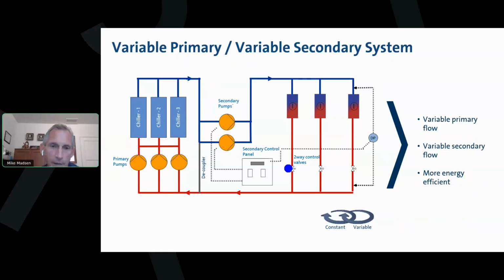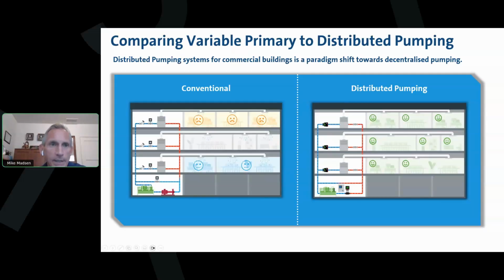They're limiting the flow, balancing the zones, and doing flow control through the air handlers, but at a pretty significant price, pretty high pressure drops through these valves. Okay, so let's look at another example of a conventional system on the left and a distributed pumping system on the right. So here I've got a variable primary system on the left.